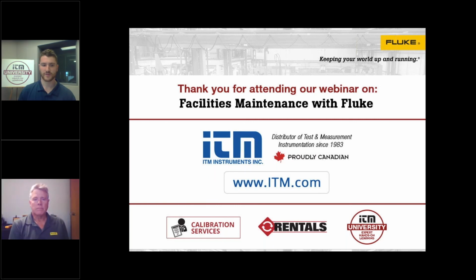Okay, all right, Dave, so we have one so far. For vibration screening with the Fluke tester, how are we going to know what's good or bad? Great question, and it's a pretty common one, one that I've heard quite a bit. The 805 FC, as I mentioned, has some intelligent screening capabilities built into the tool. One is a bearing health assessment, where on a scale, it's making a particular measurement. We call it crest factor plus, but it's really a measure of where that rolling element bearing is in the stages of wear in its life cycle. So it will give you a number which can be trended over time to see if you have any sharp changes. But there is also an automatic good, satisfactory, unsatisfactory, unacceptable message that's shown.